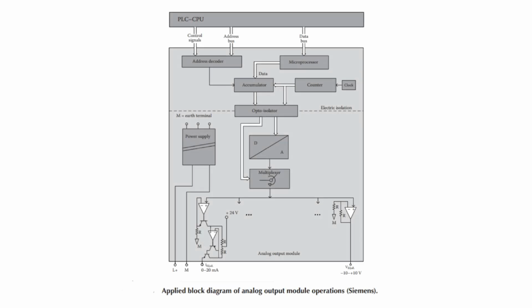The accuracy of this analog output depends on the frequency of the digital word update and is tied to the PLC, or programmable logic controller, scan cycle. So the accuracy of the analog output mainly depends upon the frequency and on the scan cycle of the PLC. Next, the figure depicts the functional block diagram of a real analog output module, which is mainly similar to the analog input module.